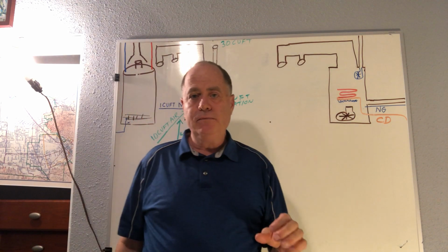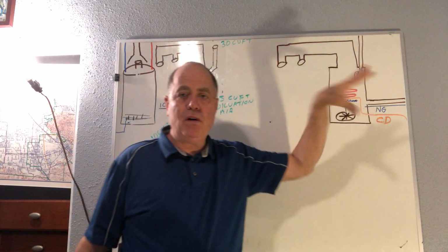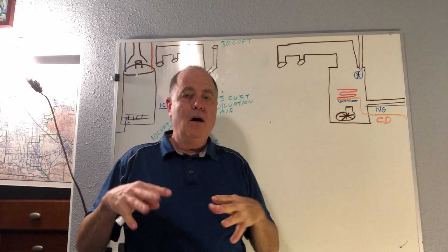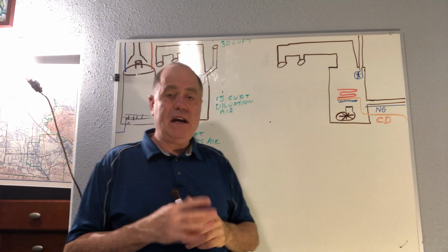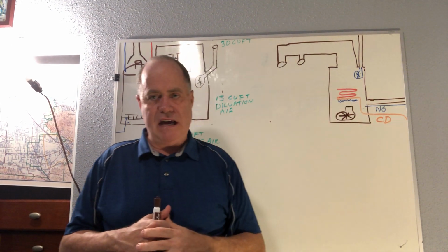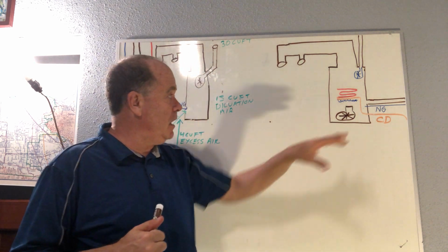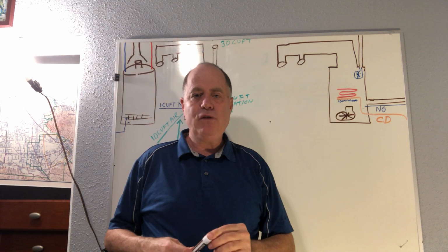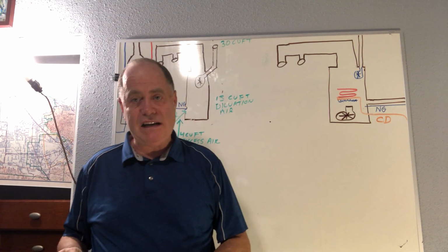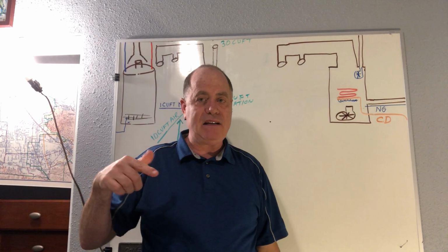As of last year, 2019, any new furnace that's put in has to be one of these high efficiency furnaces that is not relying on the air around it to mix with the natural gas. So all those calculations that are in the chapter, certainly none of that would apply to one of these new furnaces if you go to install one of them. Let me explain how they work, why they're so efficient, and a few other details about them. They've been around a while, but they've gotten better and better and more efficient. Now they're kind of mandated by law.